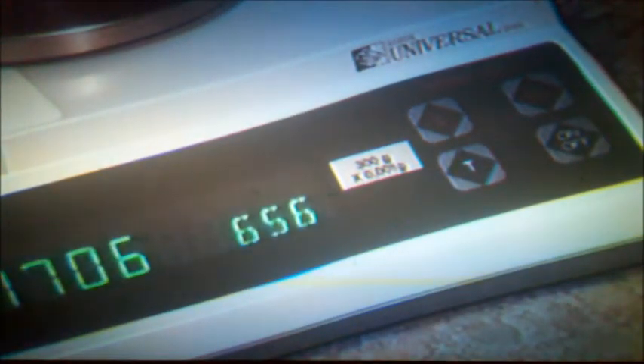At this point, it's important that the Baker Universal is switched off and on again. This will store the calibration into the Universal's memory. Simply press the on-off button twice and the system will switch off. Press it again and the system will switch back on and go through its warm-up routine again.